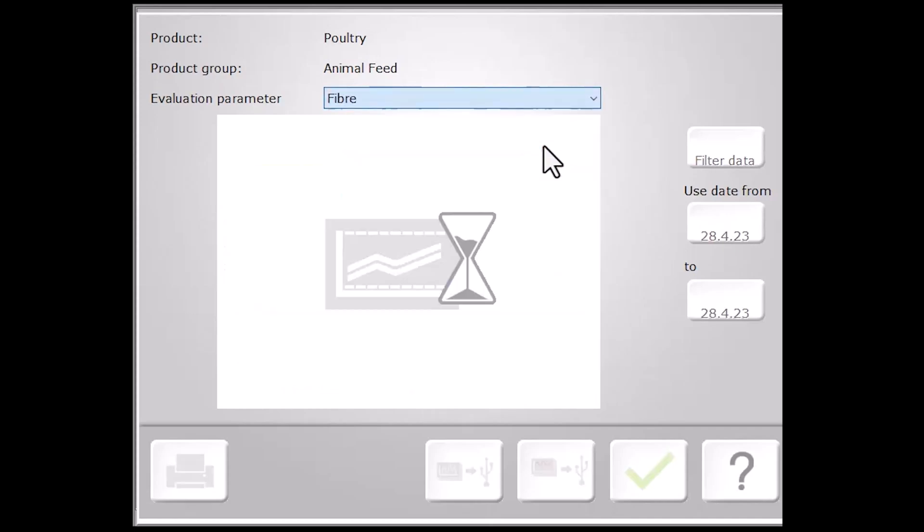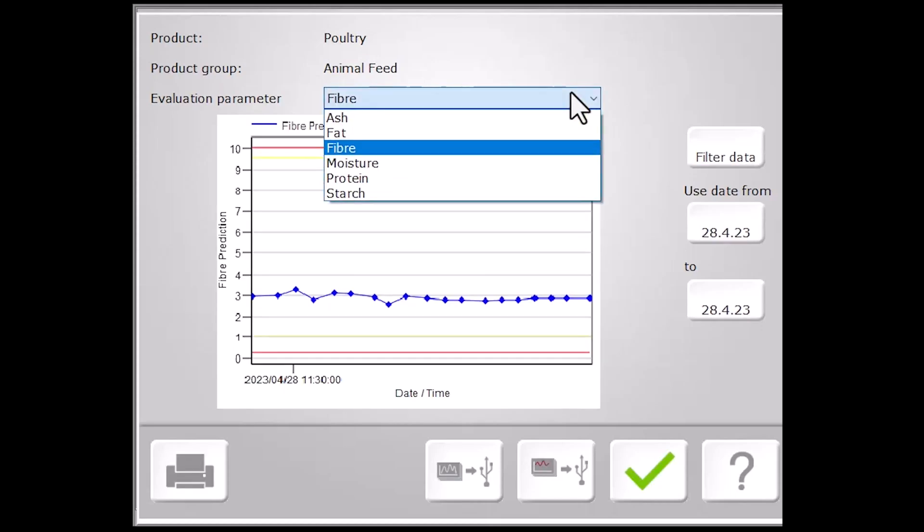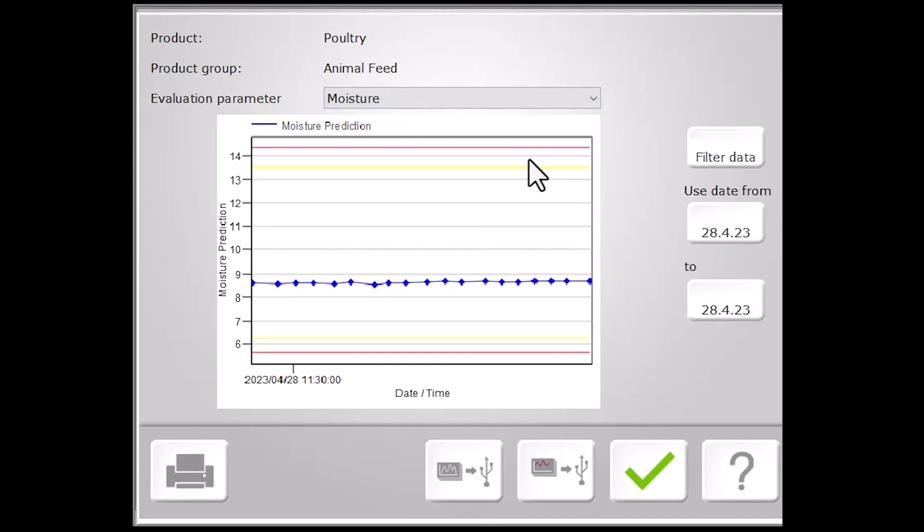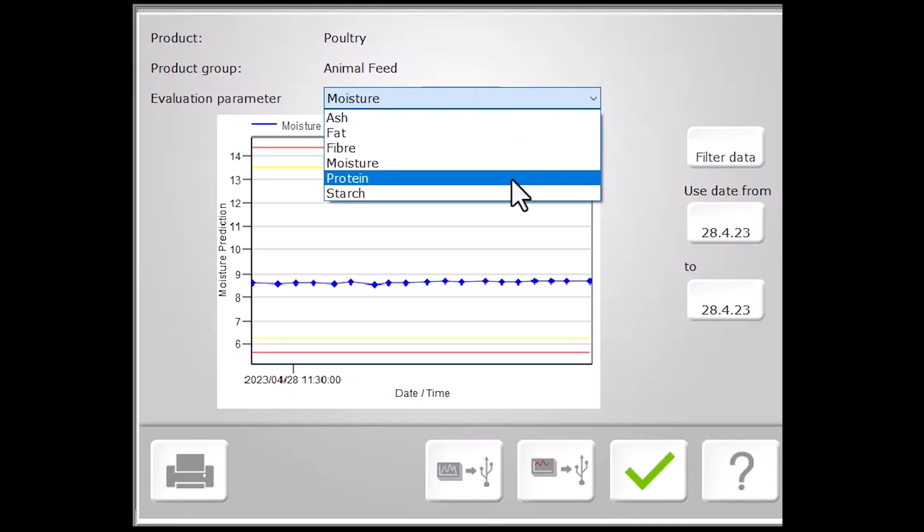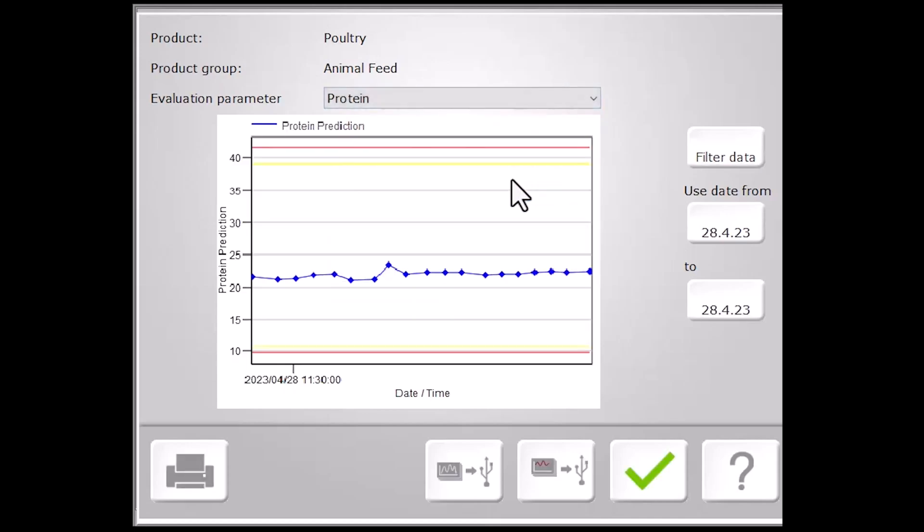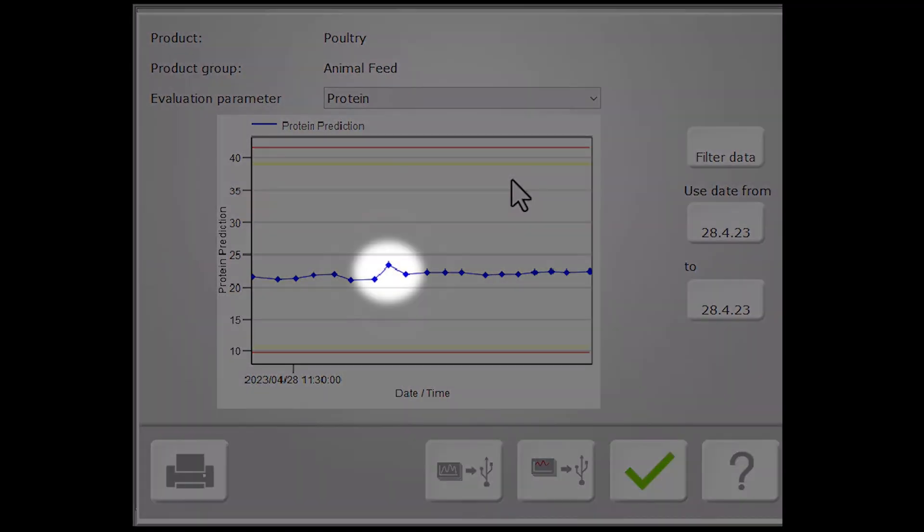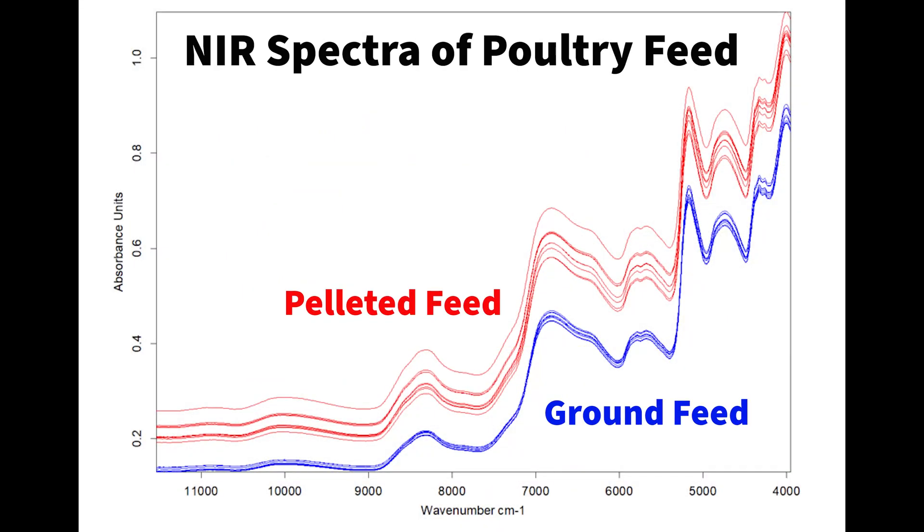We can also note how the repeatability is impacted differently from constituent to constituent, where parameters such as moisture may not be as greatly impacted. For protein, however, the difference that grinding makes is visually substantial. Here, we see about a two to three percent difference between two replicates of the same sample. And as our earlier experiments with corn indicate, grinding can improve the accuracy and precision of protein predictions by four and four and a half times respectively.